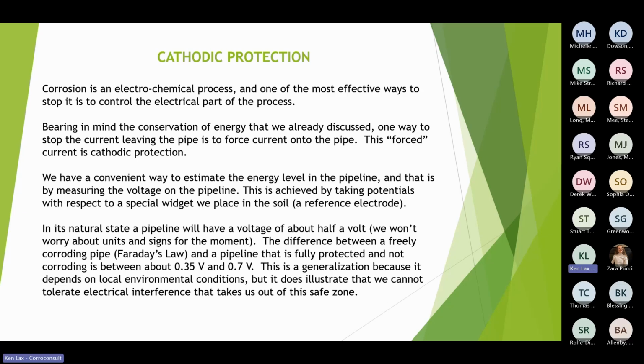Now, it's all about energy, as I mentioned earlier on, and the movement of charge and energy is everything that controls pipeline corrosion. So it's hard to measure that energy. But one of the ways we can get an idea about it is by measuring a voltage. And we measure the potential of the pipe with respect to the soil. We have a special widget that we put in the soil to give us a consistent contact, so you can compare the voltage from day to day, year to year. And we know that in its natural state, a pipeline will have a voltage of about 0.5 volt, roughly speaking. And a well-protected pipeline will have a potential of about 1.2. We won't worry about polarities for the minute. So you've only got 0.7 of a volt difference between a very well protected pipe and one that's corroding freely.